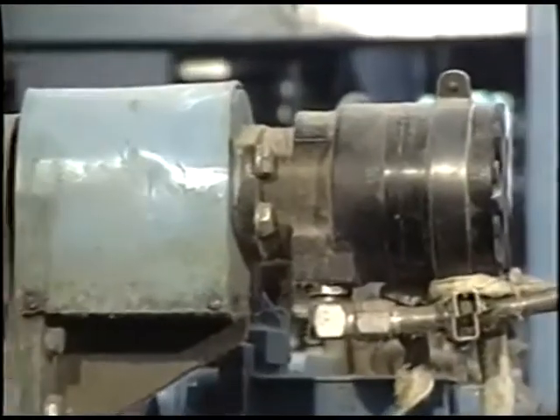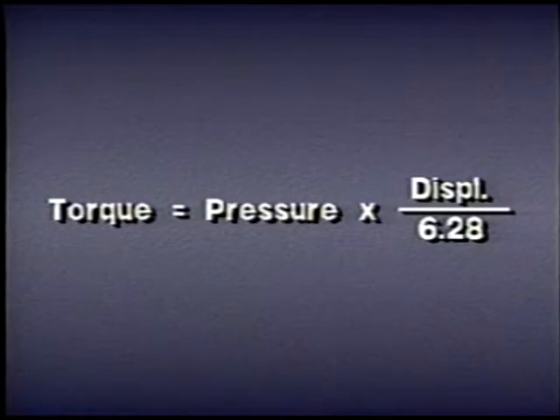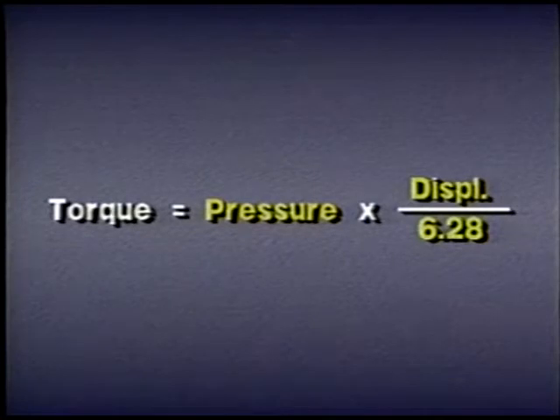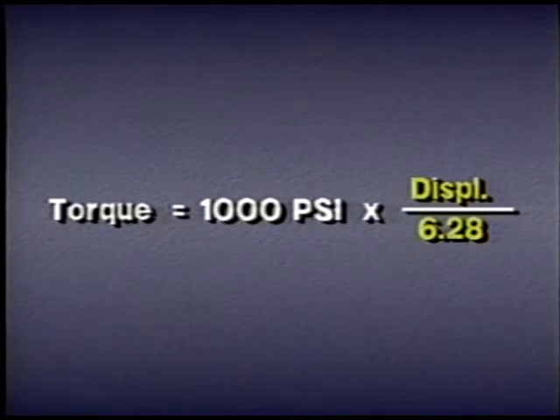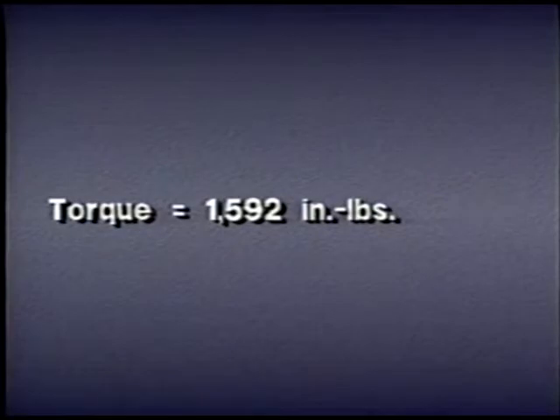Larger motors will generate more torque at the same pressure. To calculate the torque of a rotary actuator, we multiply the pressure in pounds per square inch times the displacement in cubic inches and divide by the constant 6.28. Remember, all examples assume 100% efficiency. For example, if pressure is 1,000 psi and displacement is 10 cubic inches, the torque is 1,000 times 10 divided by 6.28 — a little more than 1,592 inch-pounds.